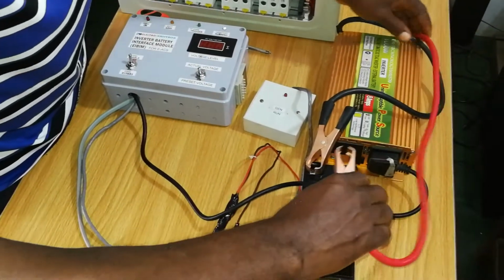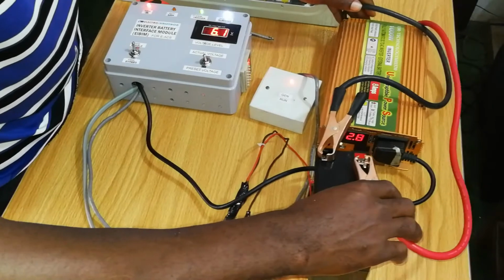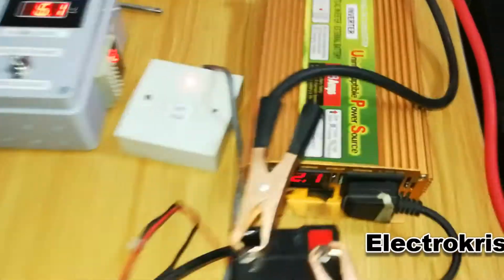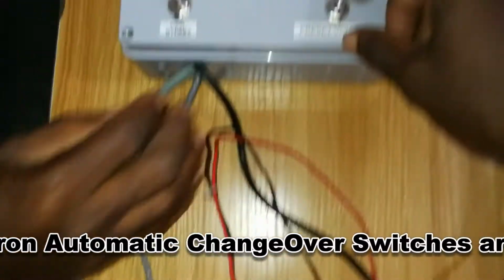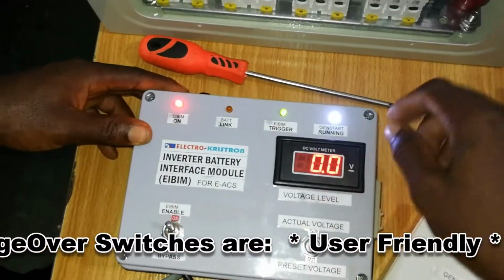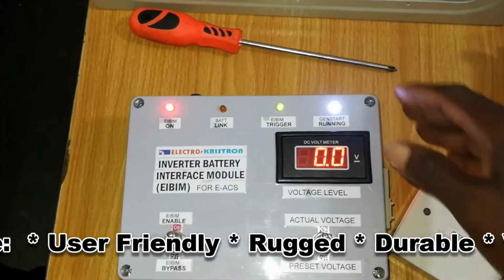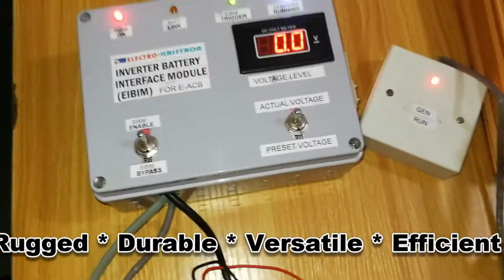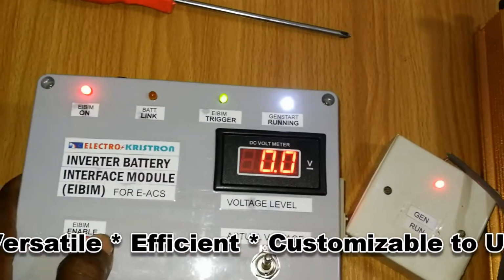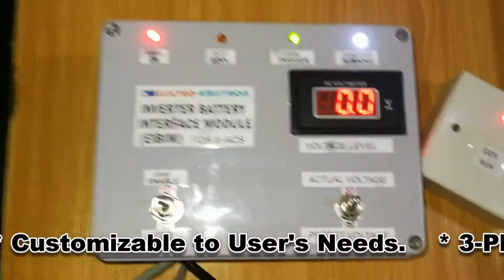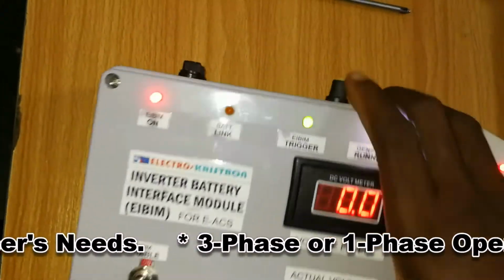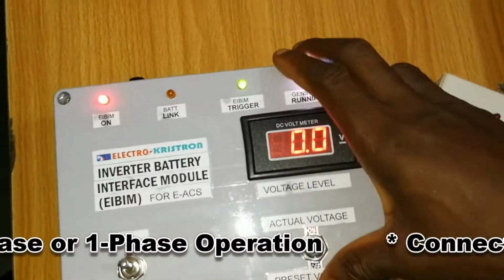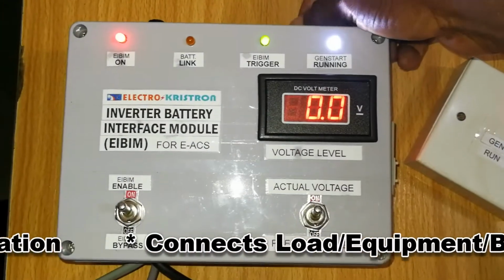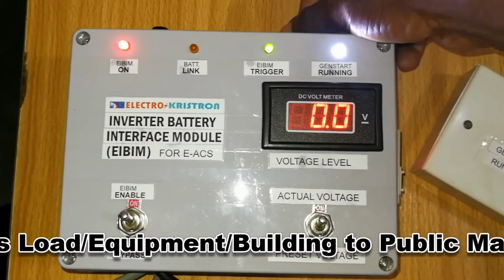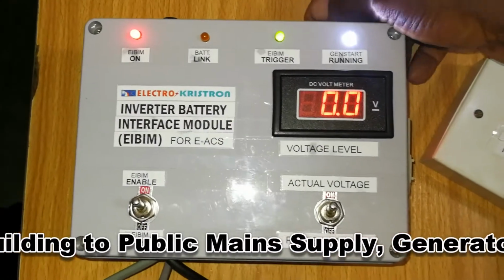Negative to negative, positive to positive. Okay, good. The inverter has come alive and our EIBIM has also come alive. Now, when you put the EIBIM on for the first time, because you have not set the threshold, the EIBIM may be in self-test mode, where you find almost all the lights coming on. Don't be alarmed, it's okay.